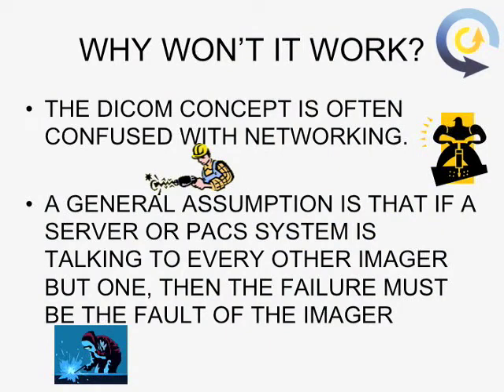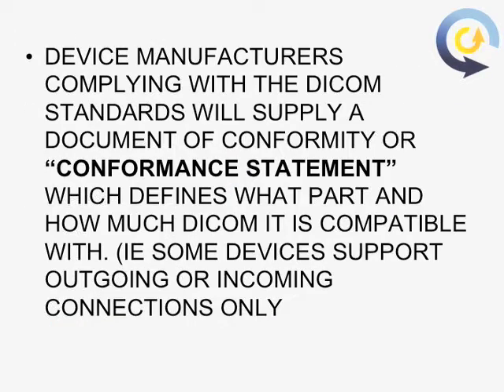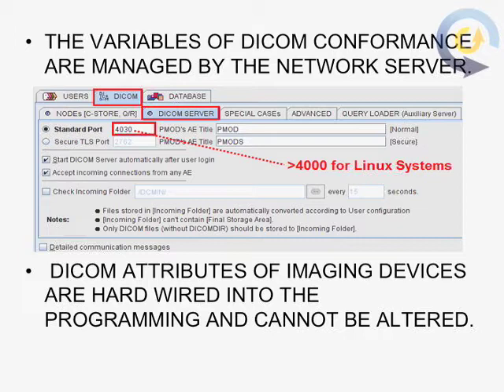Why won't it work? The DICOM concept is often confused with networking, and most users don't have a feeling for the complexity of DICOM. A general assumption is that if a server or PAC system is talking to every other imager but one, then the failure must be the fault of that imager. Device manufacturers complying with the DICOM standards will supply a document of conformity — a conformance statement — which defines what part and how much DICOM a device is compatible with. For example, some devices support outgoing or incoming connections only.